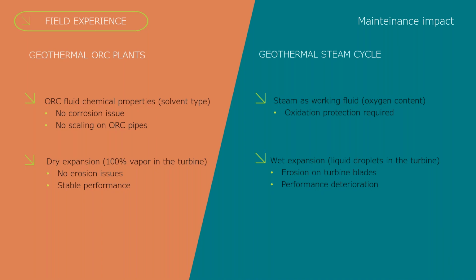So in steam cycle operation, it is essential to have in mind specific chemical treatment practices that are inevitable to guarantee oxidation protection of the internal surfaces of the plant. In the case of ORC plants, the working fluid belongs, from a chemical point of view, to the family of solvents. So there is no oxygen, and it is a closed loop, meaning there is no issue of corrosion in the internal piping and equipment of the plant.